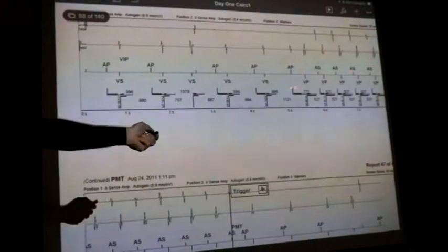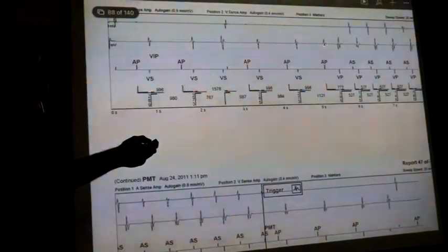And then what's happened to the ventricular electrodes? The ventricular signal? You can't see it, can you? The ventricular lead has not sensed this signal, because this is in ventricular blanking. So when you atrially pace, and only when you atrially pace, you blank the ventricle. Because this is maybe 3 volts, and next door in the ventricle, we're trying to detect something as low as 2 millivolts. So that's thousands of times smaller. So we have to blind the ventricular channel for a short period of time. So A pace blanks the V, pseudo-pseudo-fusion beat.